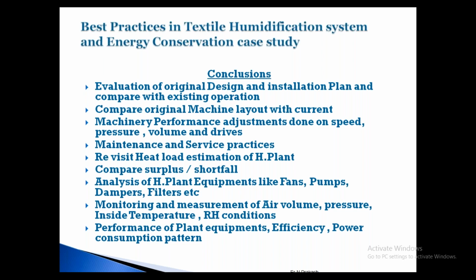Speed adjustment: normally they run at a particular speed, but after installation they change the speed, the pressure and the volume. In the case of the waste collection system, for carding and other machines, the pressure and volume change. Volume is very important for your humidification plant, because with a single fan or double fan, they add extra pneumafil and compact air. Suddenly they put compact air in separately.